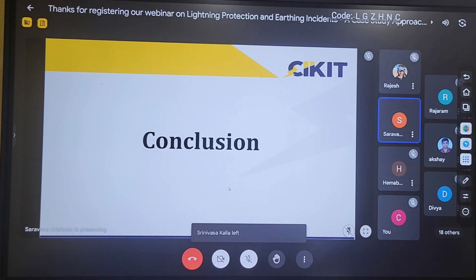The conclusion of today's session: the first one is risk assessment calculations. There are so many parameters involved in performing the risk assessment calculation, and we cannot randomly select the suitable level for a particular site condition. So customized calculations should be performed to determine whether a lightning protection system is required for the particular site or not. If the value of risk is less than RT without a lightning protection system, it means that a lightning protection system is not mandatory for the particular site conditions. That does not mean that lightning won't strike the particular buildings and structures. Even if lightning strikes, the risk due to lightning will be lower on those site conditions. For additional protection, if we need, we can install level 4 protection. And based on the risk assessment calculations only, we have to perform the design of the lightning protection system.